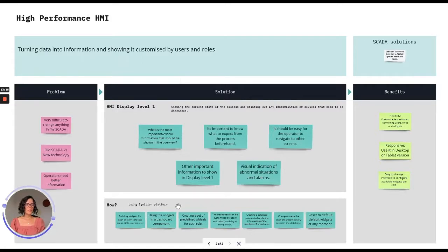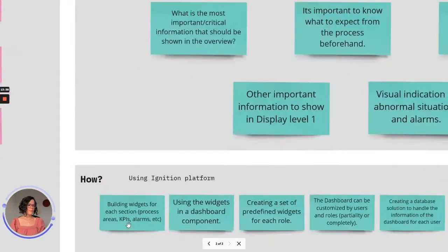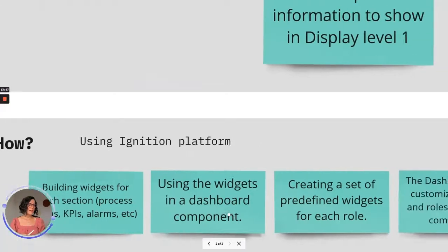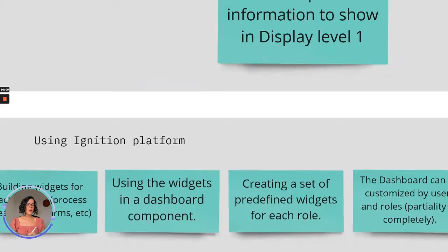So how do we do it using the Ignition Platform? First, we build widgets for each of the tiles — widgets for process areas, KPIs, and alarms — and we have these shown in a dashboard component. So we have the flexibility to turn widgets on and off, and also to move them or organize them on the screen as we want.